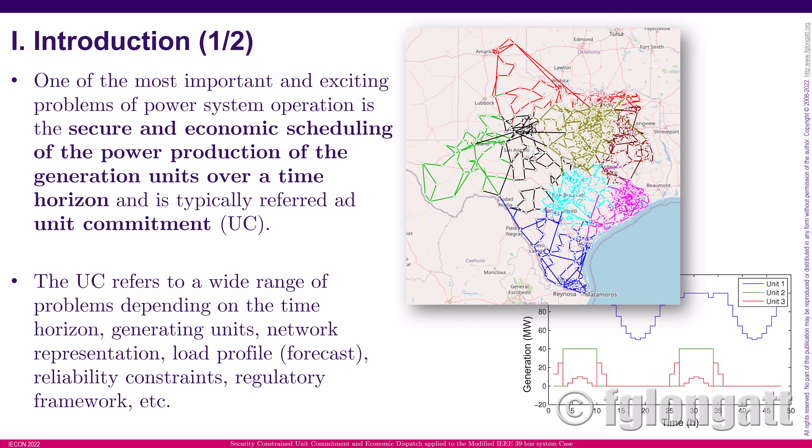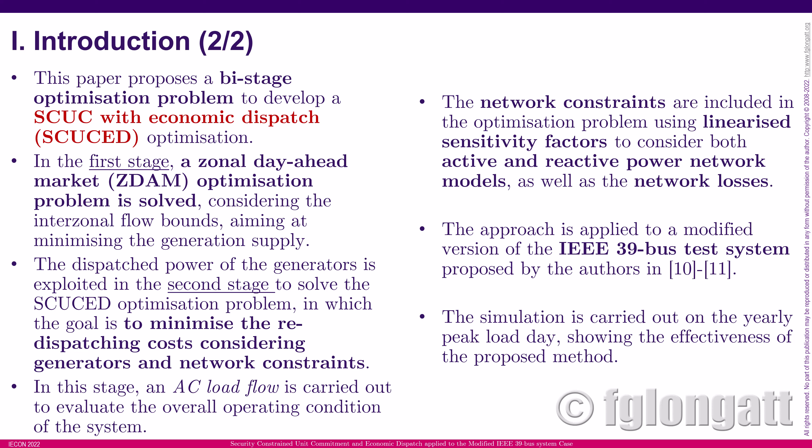In this paper, what we are proposing is basically a two-stage optimization problem to develop a security constrained unit commitment with economic dispatch optimization — what we call the SCUCED. In the first stage, a zonal day-ahead market optimization problem is solved considering the interzonal flow bounds, aiming to minimize the generation supply. The dispatch from that stage is then used in the second stage to solve the secure optimization problem, where the goal is to minimize the redispatching costs considering the generator and network constraints, using an AC load flow non-linear formulation.